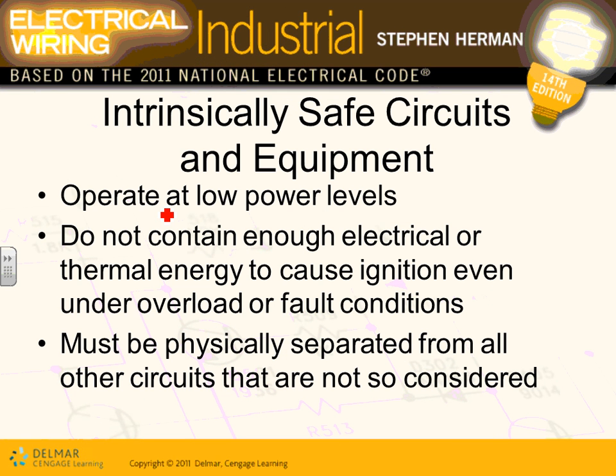Okay, groups. There's something called intrinsically safe circuits and equipment. Intrinsically safe circuits and equipment, Adam, are sensors and instrumentation. These are low voltage equipment that sense. For example, inside the gas tank, you need to know the height of the gas inside that tank. You want to sense the gas height, the pressure. How are you going to sense these?